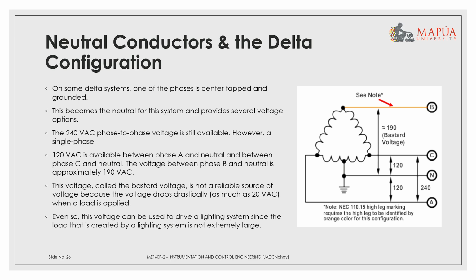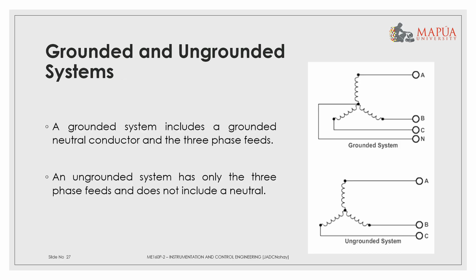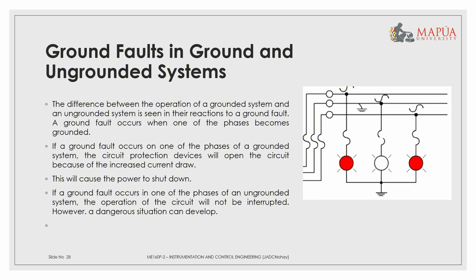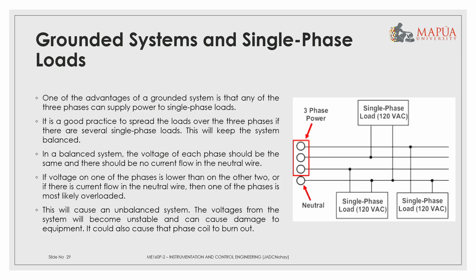So, these are the slides. The advantage of a grounded system is balance and safety, while the advantage of an ungrounded system is that operations can continue even if one phase is lost. However, ungrounded systems also hide faults, making them hazardous.